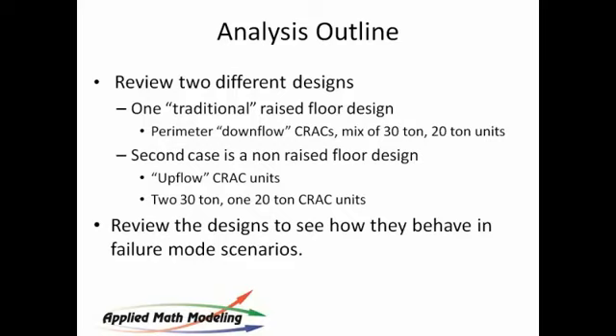So we're going to look at a couple different designs. We're going to look at a traditional raised floor design. It is what they call a perimeter design: the cooling units are arranged around the outside of the room. They are downflows. The air is blowing down into the subfloor, the raised floor. And in this case, it's going to have a mix of 30-ton and 20-ton cooling units.